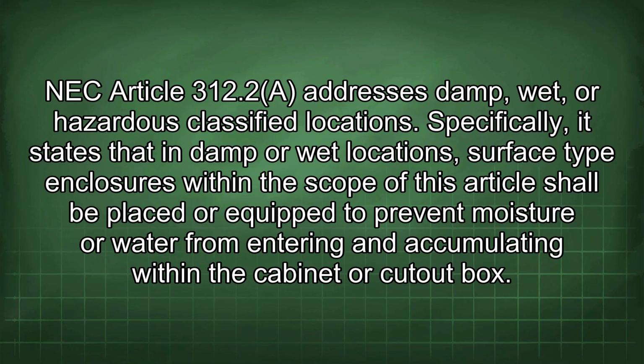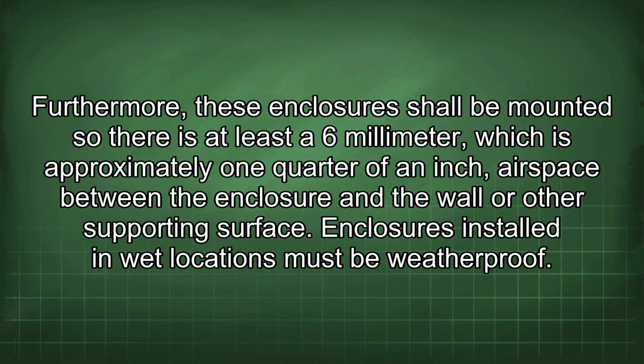NEC Article 312.2 addresses damp, wet, or hazardous classified locations. Specifically, it states that in damp or wet locations, surface-type enclosures within the scope of this article shall be placed or equipped to prevent moisture or water from entering and accumulating within the cabinet or cutout box. Furthermore, these enclosures shall be mounted so there is at least a 6 mm, which is approximately 1/4 of an inch, airspace between the enclosure and the wall or the supporting surface.